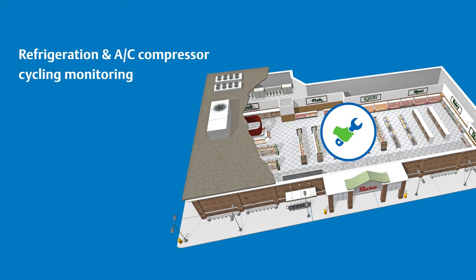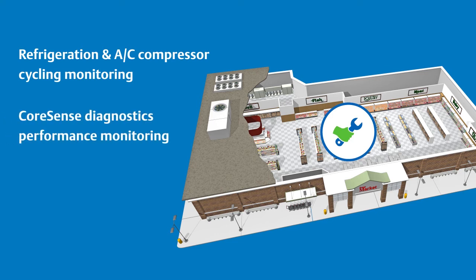Condition-based maintenance can be used on a variety of refrigeration applications to help minimize or prevent downtime and protect your equipment investments. In compressors, high cycling can increase energy use by as much as 10 percent, while high superheat decreases system efficiency. Condition-based maintenance uses refrigeration and AC compressor cycling monitoring, CoreSense diagnostics performance monitoring, and return gas monitoring. These features allow for faster and more accurate diagnosis to prevent failure and extend the life of your equipment. Severity-based advisories also optimize dispatches.